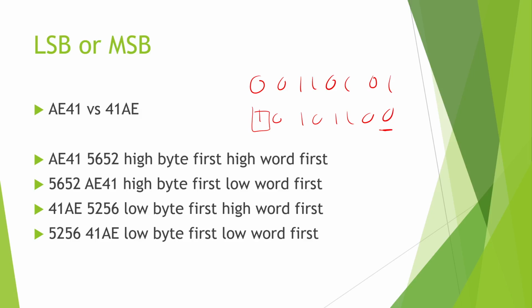Which means in your code you have to be really backwards, because you have to say I need sensor input 8 when you really need sensor input 1. It's just a matter of flip-flopping things if you can't figure out how to fix it. So technically you could brute force this in a really bad situation. You have to leave really heavy notes somewhere about why your code is funky. But technically you could just brute force it in your PLC, going input 8 is what I need when really you need input 1, as long as you stay consistent.